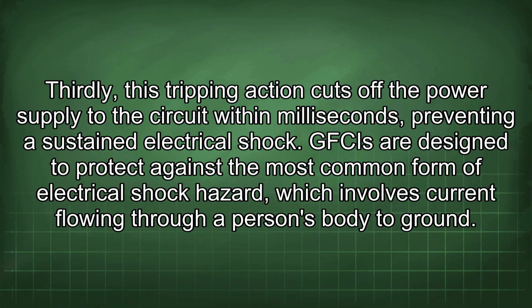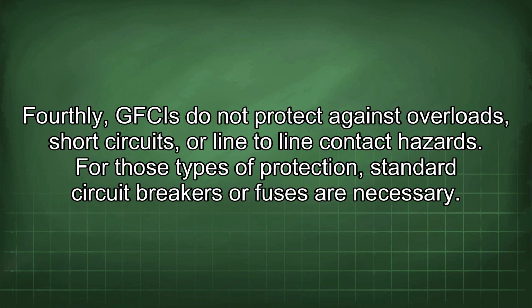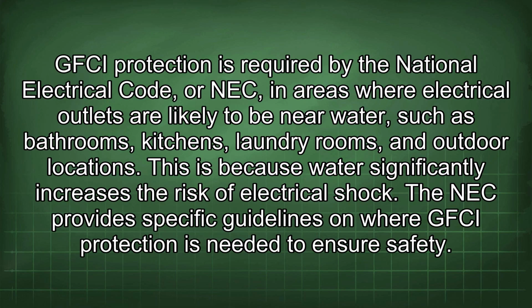GFCIs are designed to protect against the most common form of electrical shock hazard, which involves current flowing through a person's body to ground. Fourthly, GFCIs do not protect against overloads, short circuits, or line-to-line contact hazards. For those types of protection, standard circuit breakers or fuses are necessary. GFCI protection is required by the National Electrical Code, or NEC, in areas where electrical outlets are likely to be near water, such as bathrooms, kitchens, laundry rooms, and outdoor locations. This is because water significantly increases the risk of electrical shock. The NEC provides specific guidelines on where GFCI protection is needed to ensure safety.